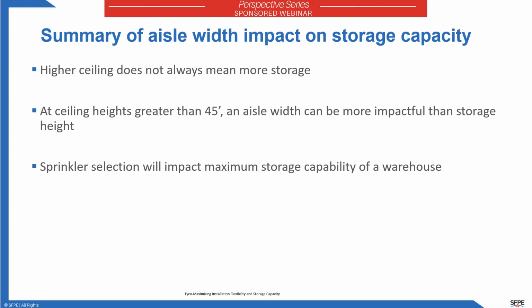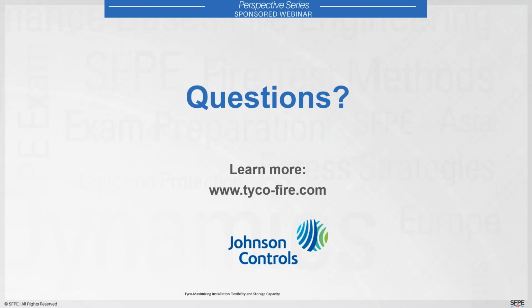So in summary for today's presentation, the two attributes that I talked about, both the ceiling to sprinkler distance and the aisle width that's approved for sprinklers, have an impact both on the flexibility during installation as well as the amount of warehouse capacity available based on the fire protection scheme. And these are two fairly significant attributes when it comes to selecting ESFR protection schemes for warehouse protection. And with that, I will open it up to any questions.